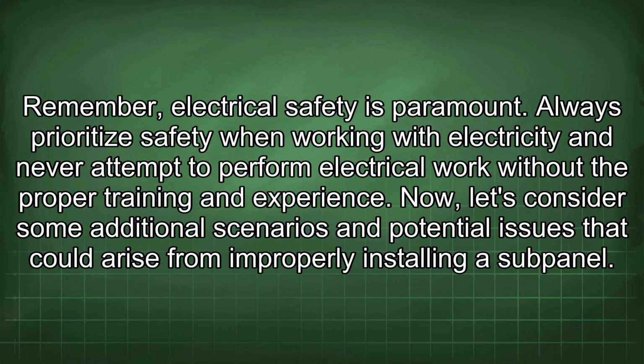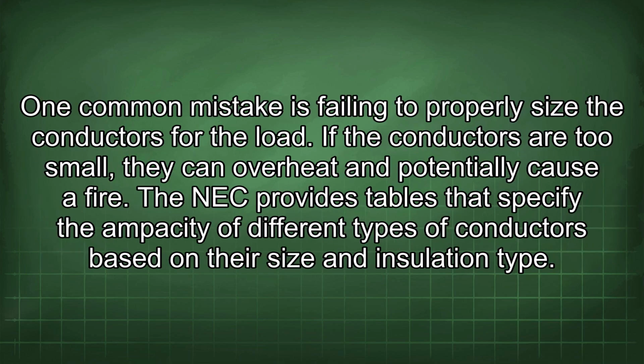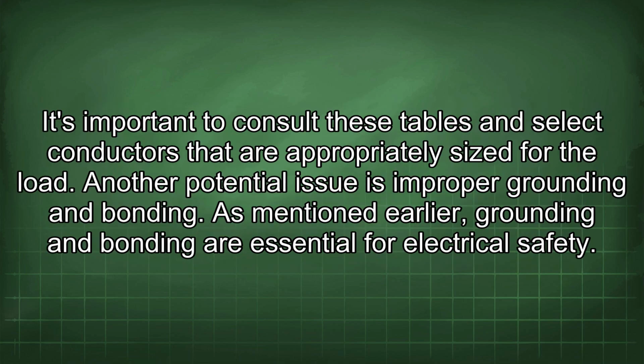Now, let's consider some additional scenarios and potential issues that could arise from improperly installing a subpanel. One common mistake is failing to properly size the conductors for the load. If the conductors are too small, they can overheat and potentially cause a fire. The NEC provides tables that specify the ampacity of different types of conductors based on their size and insulation type. It's important to consult these tables and select conductors that are appropriately sized for the load.